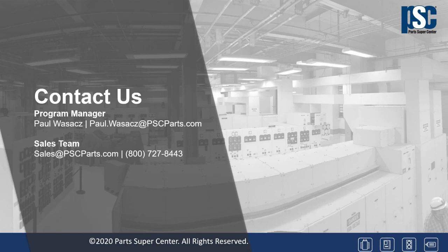The next question is, does PSC offer switchgear retrofitting to include all the SALs? So there's 2 parts to that question. The first is the circuit breaker, and the second is the cubicle. So for the circuit breaker, through the network of the former GE shops, which are now ABB, we can provide upgrades to your circuit breakers to incorporate all the recommended service advisories. Or if you would prefer to put a roll-in retrofit breaker into the cubicle, we can provide a brand new vacuum retrofit breaker that will meet all the requirements of the original switchgear, and all the interface points will fit as originally designed. With respect to the cubicles, we can take the summary number of the switchgear and we can look to see, again, what service advisories apply to that particular switchgear.